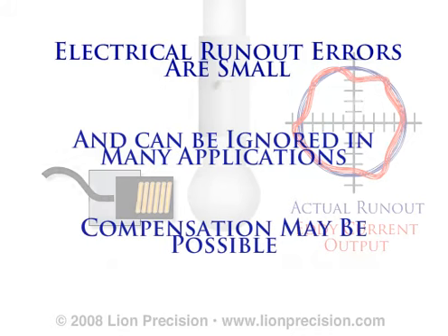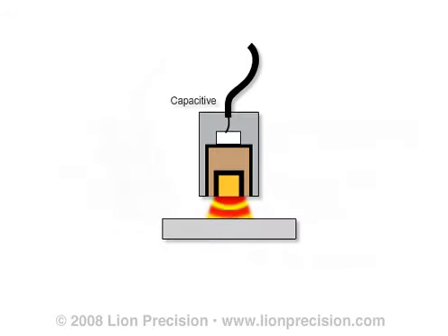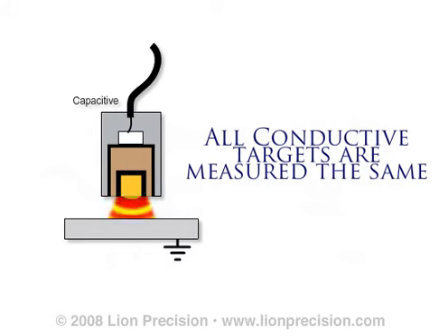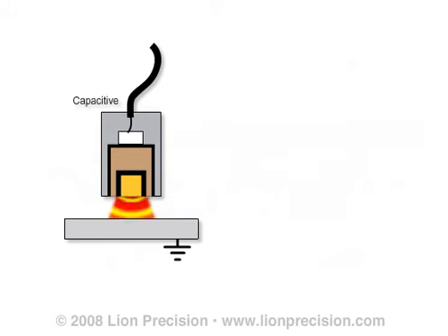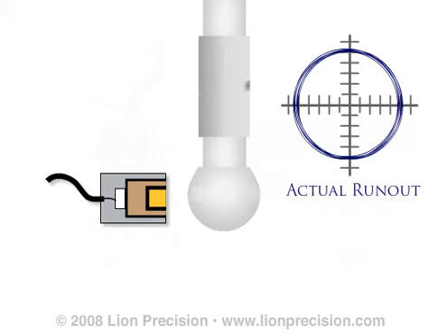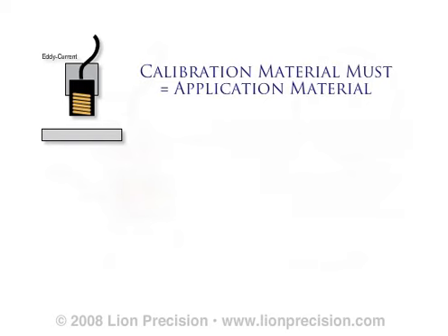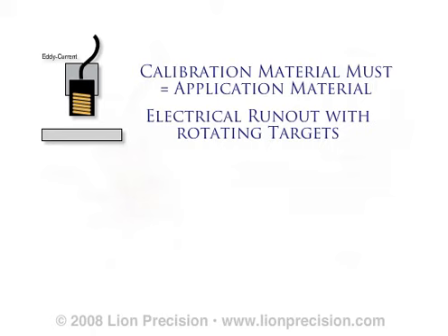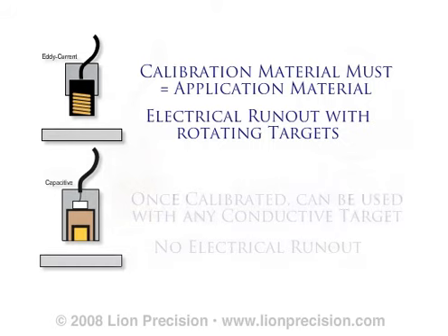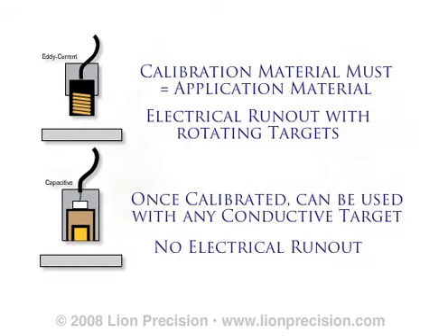as capacitive sensors. The electric field of a capacitive sensor uses the target as a conductive path to ground. All conductive materials offer this equally well, so capacitive sensors measure all conductive materials the same. Once a capacitive sensor is calibrated, it can be used with any conductive target with no degradation in performance. Because the electric field of a capacitive sensor does not penetrate the material, variations within the material do not affect the measurement. Capacitive sensors do not exhibit the electrical runout phenomenon of eddy current sensors and can be used with rotating targets of any conductive material without additional error. Eddy current sensors should be calibrated to the same material as the target in the application and should not be used with rotating targets unless the electrical runout errors are acceptable in the application. Capacitive sensors, once calibrated, can be used with any conductive material with no material-related errors.